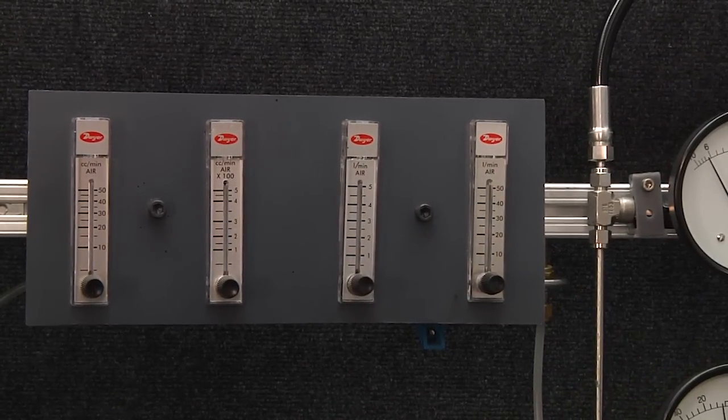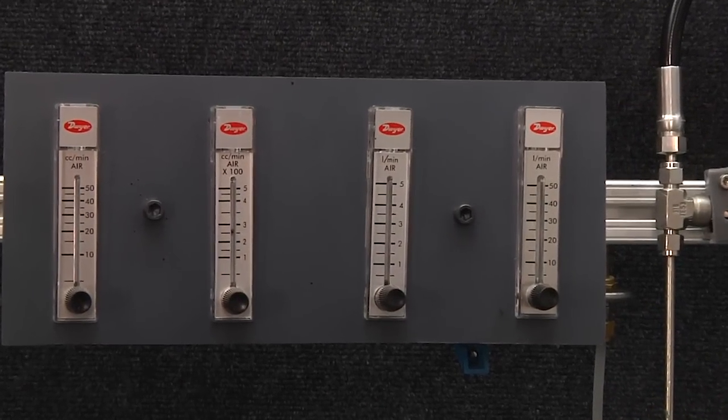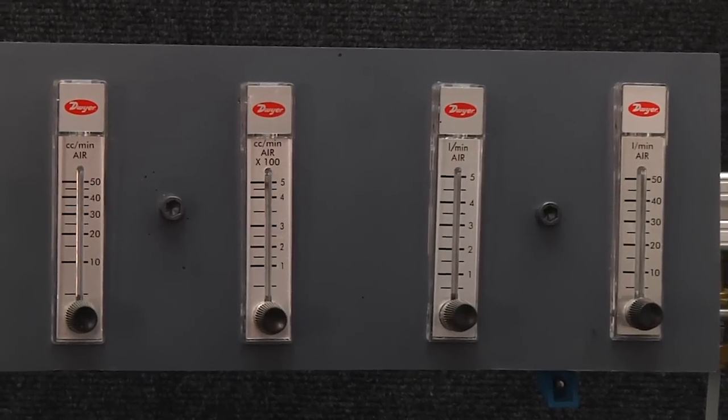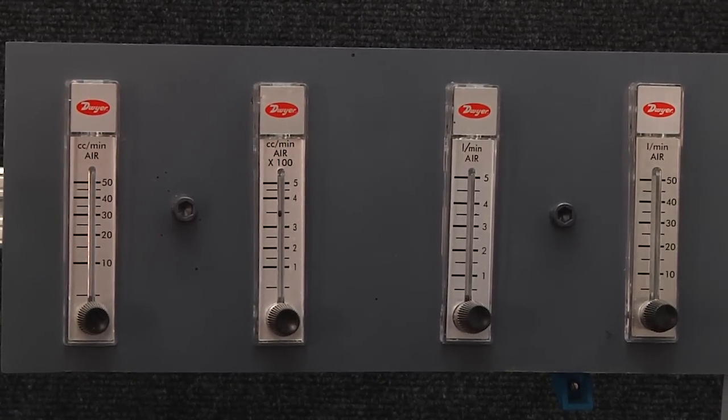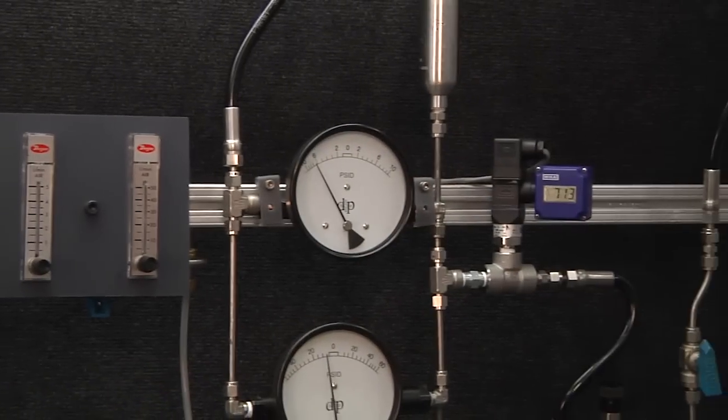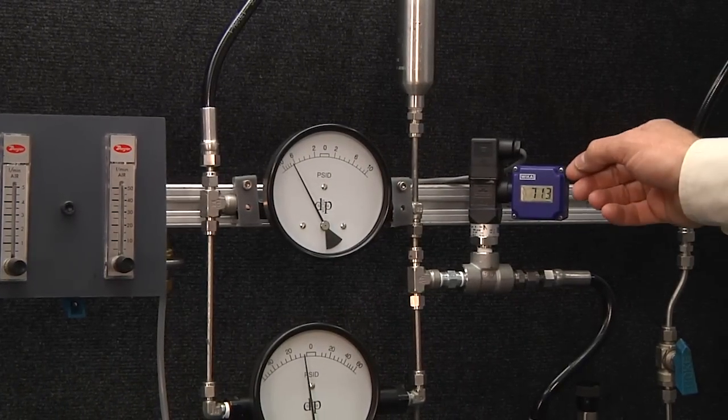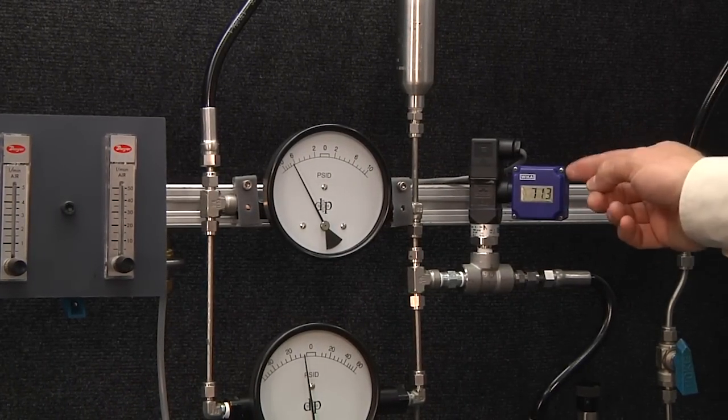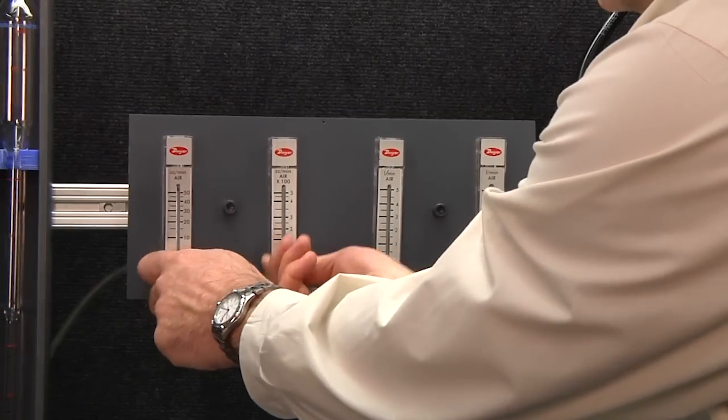I'm going to adjust the needle valve and try to get it in the three to four hundred cc's per minute range. There we are, and again we're still seven psi above the pilot set point and at 713 psi on the inlet. So widely varying flow rate changes.